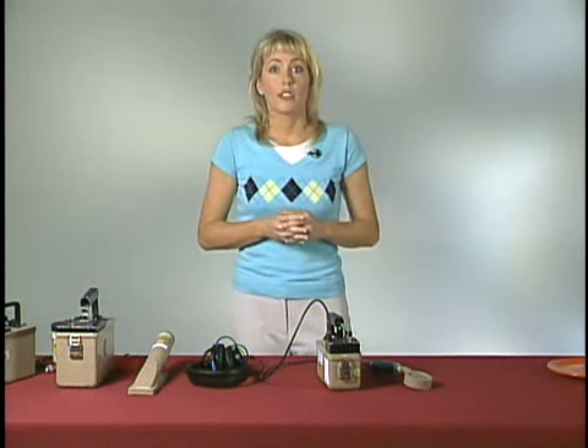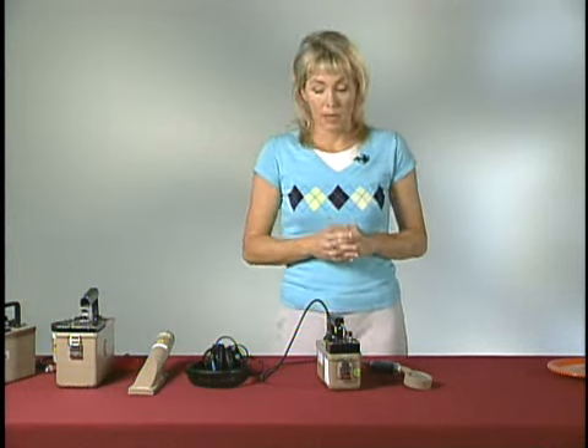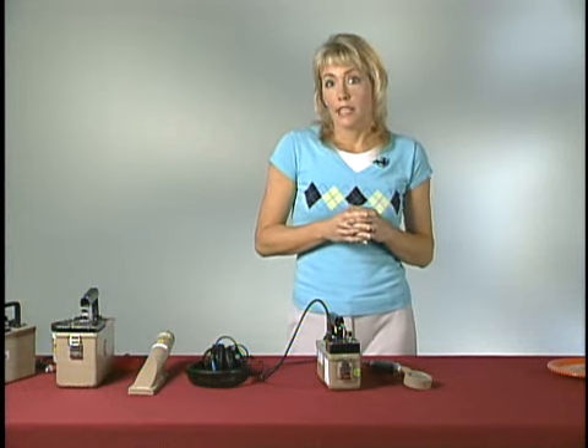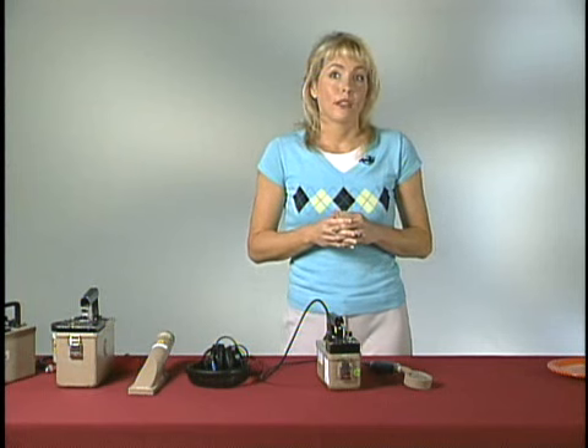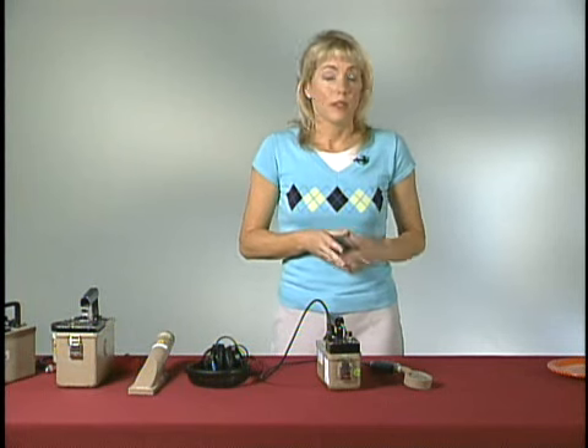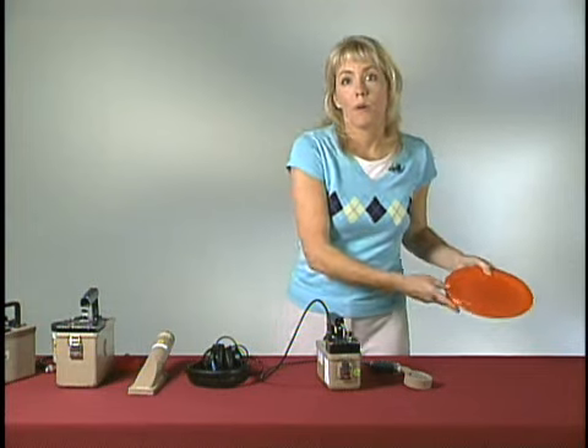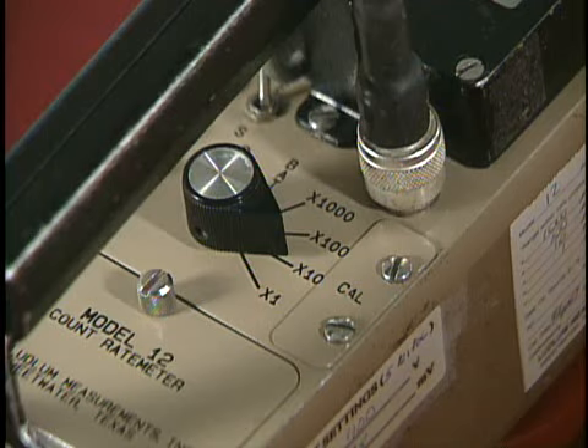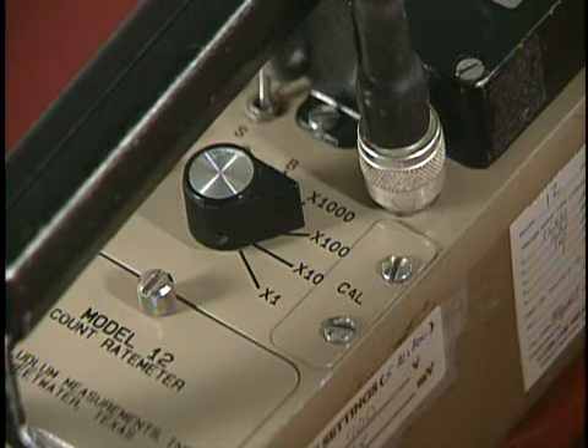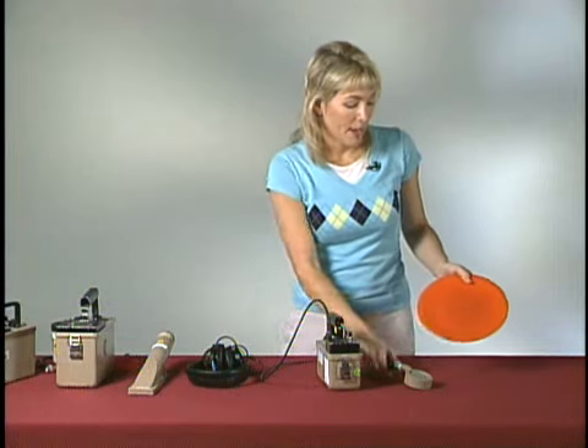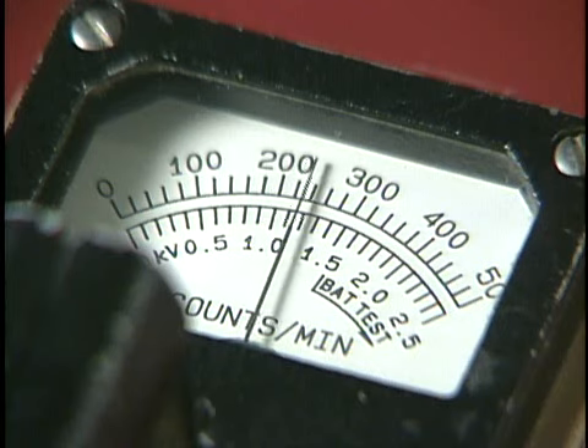Next, we need to conduct a source check to make sure the meter is working properly. With the meter on, place the detector close to the radiation source, such as a thorium-containing gas lantern mantle, an orange Fiesta ware plate, or a plastic button check source. With the appropriate range selected, probably times 10 or times 100, verify that the meter responds. It's not a bad idea to indicate the reading on a label and stick the label on the side of the case. That way, the next time you check the GM, you will know if its response is changing.